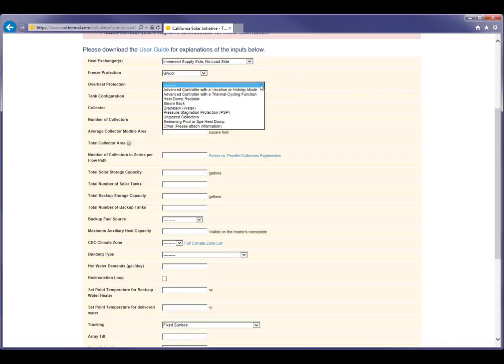So we require that there's some sort of overheat protection method that's employed to prevent that from happening. And there are a number of methods out there. It's possible to dump excess heat to a pool or a spa, use some sort of a heat dump radiator, or there are various control strategies that can achieve that, like controllers that will run the thermal cycling at night in order to generate load so that the system doesn't get into a stagnation mode in the subsequent day.